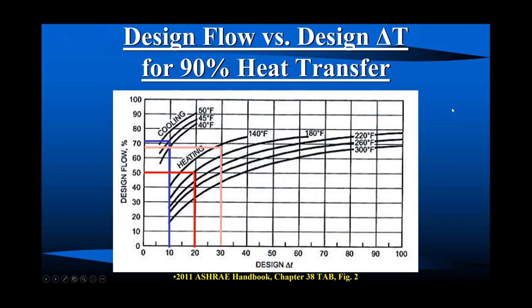We take a little bit further look. If I had an air-to-water heat pump system and had it only supply 140 with 30 degree delta T, now it's really close to the lack of tolerance of a chilled water system. What about a 12 degree chilled water system? Even less tolerant of a lack of flow, if you will. What is the most difficult system there is to balance? Right. This kind of trend here is the higher the delta T, the more difficult it is to balance. Not this system, though. The sensible cooling system, 5 degrees at 58, is the most difficult hydronic system there is to balance. The sensible only cooling system takes the cake.